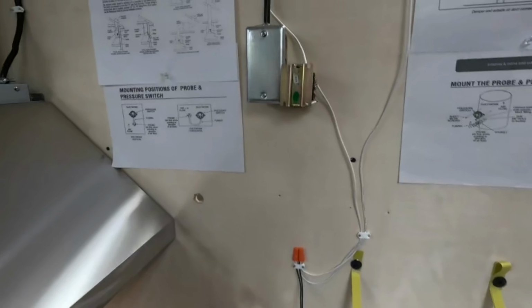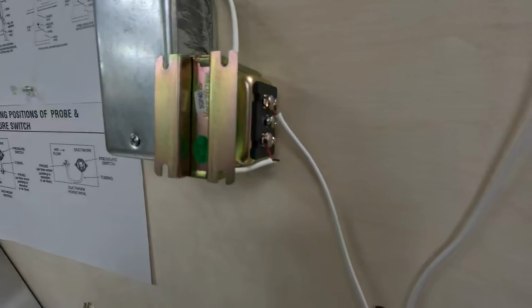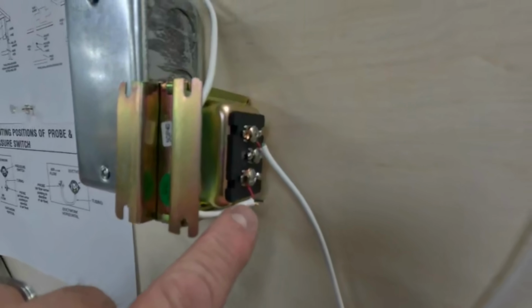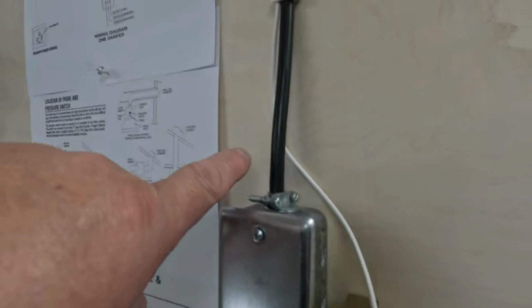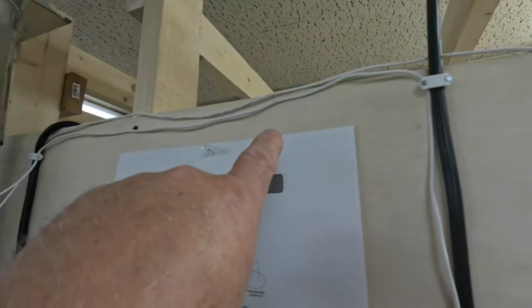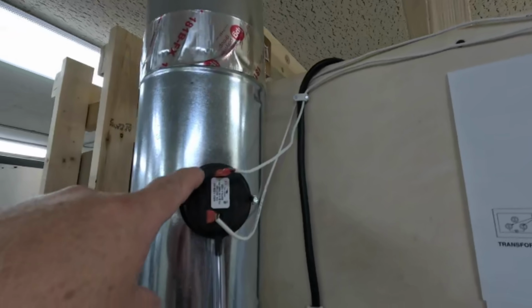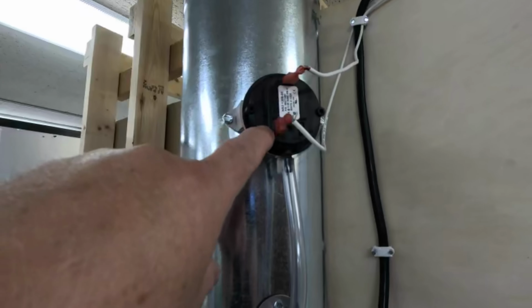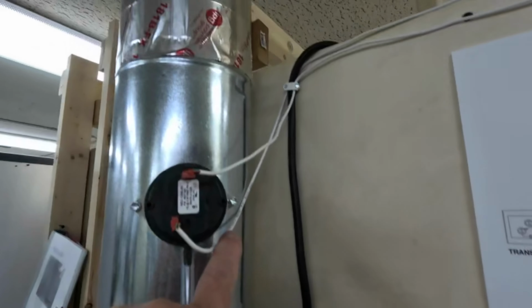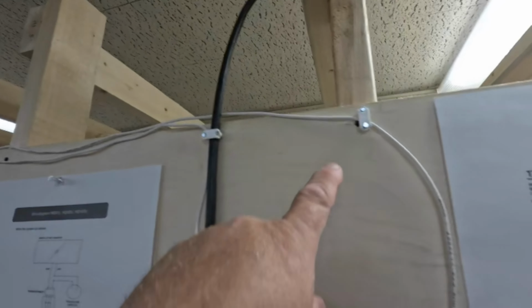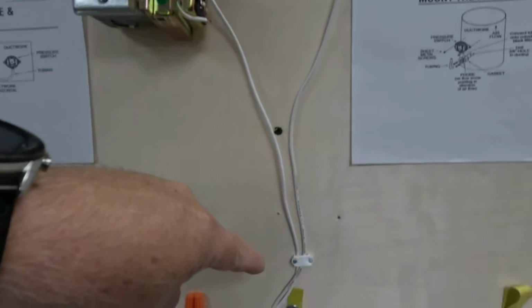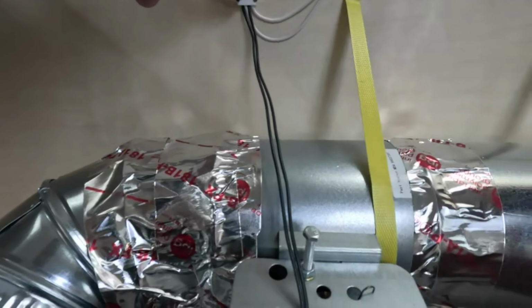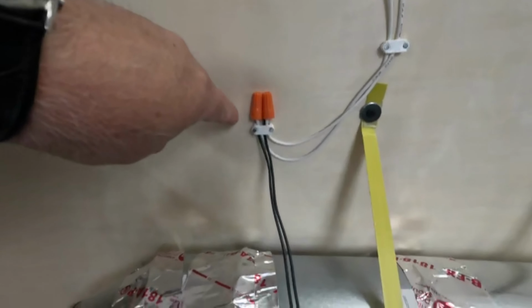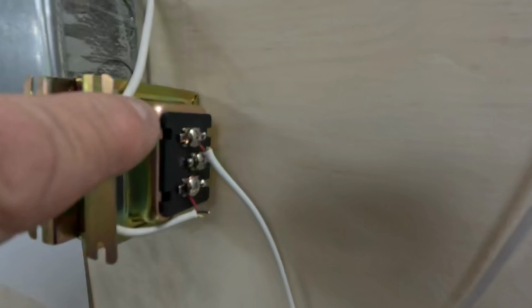So how this unit works and how it's wired, if you take a look off of the terminal here on the transformer, I have low voltage wiring running up to one side of the pressure switch. Off the other side of the pressure switch, I have low voltage running all the way up, coming back down to one side of that makeup air damper. And off the other side of the makeup air damper, it goes back to the other side of that transformer.